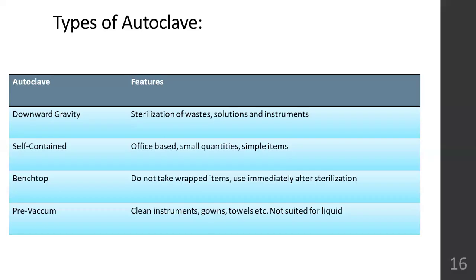Then self-contained autoclaves. These are office-based, small quantity, simple items can be sterilized. These are self-contained sterilization, so you don't have to send the instrument to the CSSD. This small self-contained unit can be kept on one board. Benchtop also. You don't have to wrap the items to do the sterilization, but you have to use it immediately after sterilization. So in ICU and emergency departments, where you can't afford to waste time waiting for the equipment to arrive to do some procedures, that benchtop is used. So they don't take any wrapped items. You have to sterilize the item as it is. As soon as flash sterilization is done, immediately use the instrument.